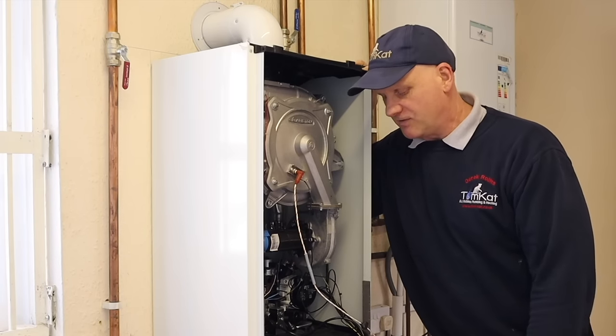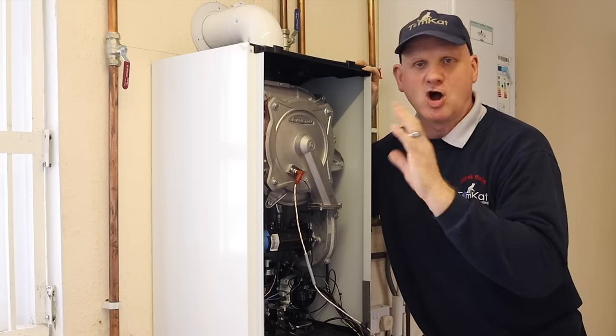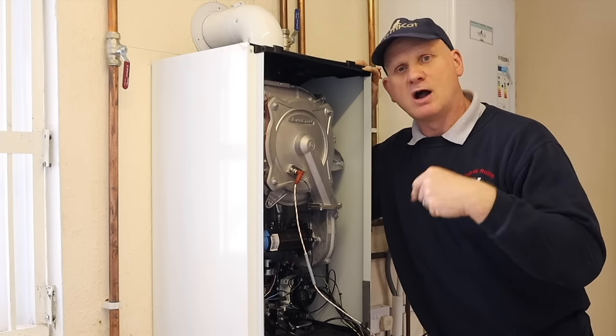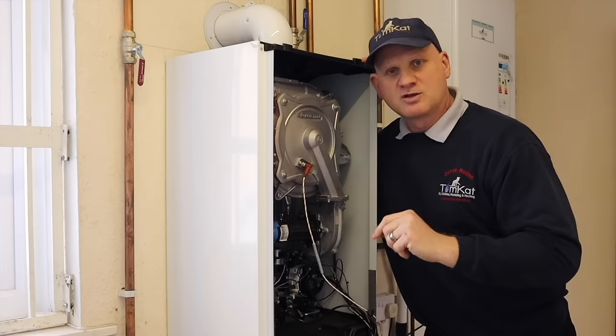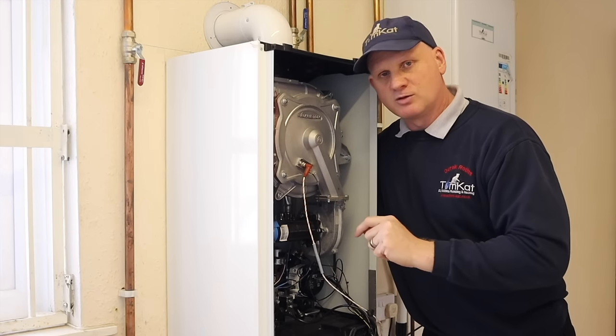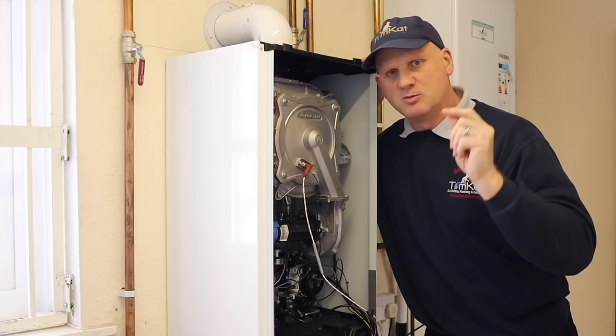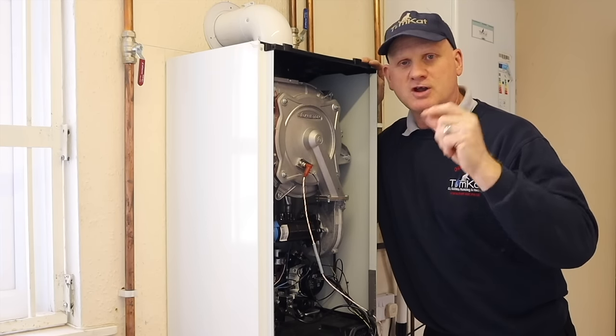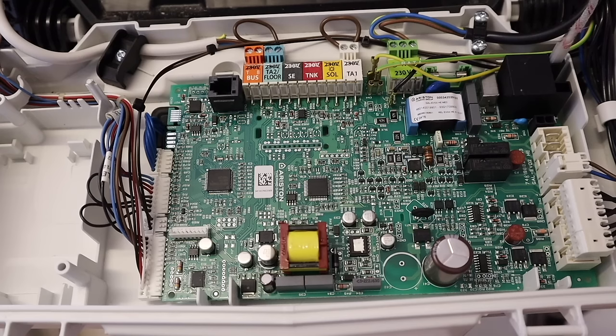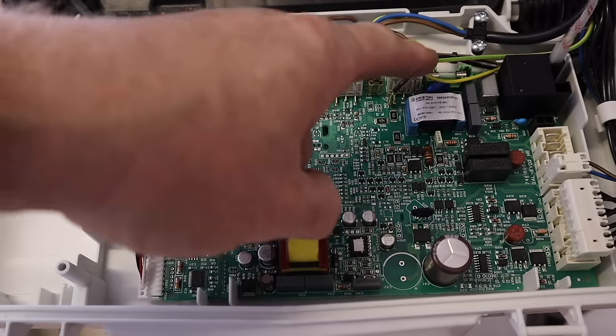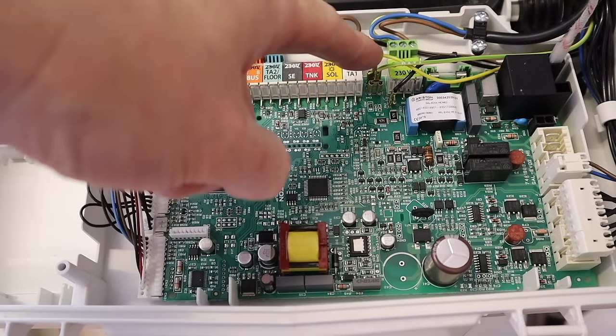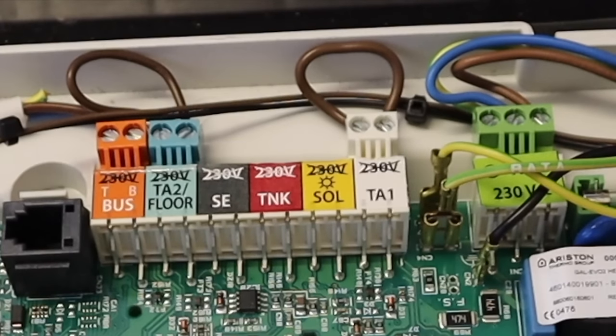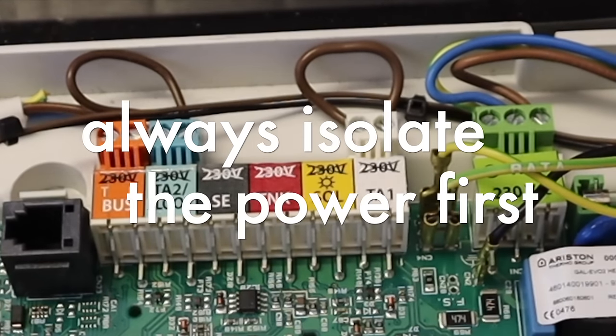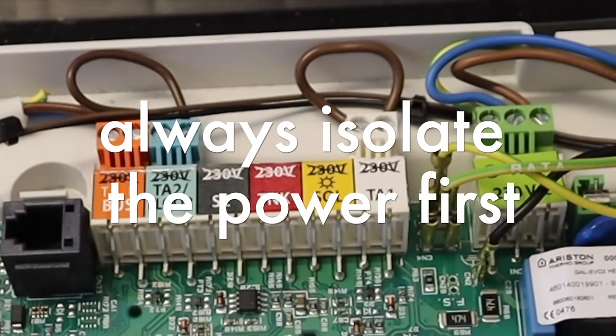Now, OpenTherm was invented by Honeywell and has been made available for all manufacturers to use. A recent study, out of 28 heating controls, found 74% of them were using the manufacturer's controls, and the rest were using OpenTherm. Now, if we look at this printed circuit board on this Ariston boiler, we can see these are our connections at the top here. Always remember, guys, never open this up unless you've followed your safe isolation procedures, because one thing you don't want to be doing is sticking your fingers in and getting electrocuted.